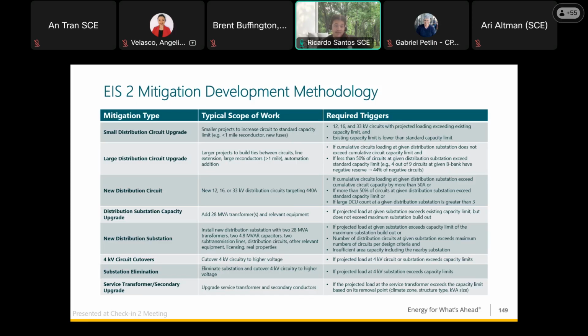The necessary triggers for a large DCU require 2 conditions to both be met: the cumulative circuit loading at a given distribution sub does not exceed the total capacity circuit limit, and fewer than 50% of the circuits exceed their capacity limit. For example, if a substation has 4 of 9 circuits above the circuit capacity, we would elect to build a large distribution circuit upgrade rather than step to the next solution, which would be a new circuit.